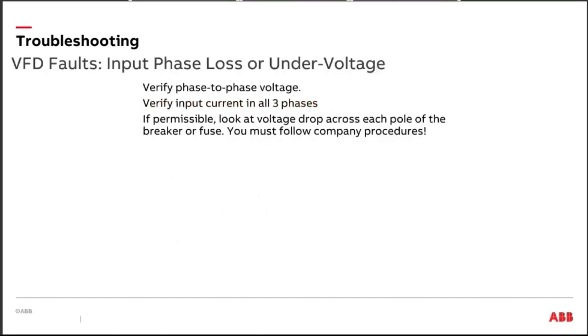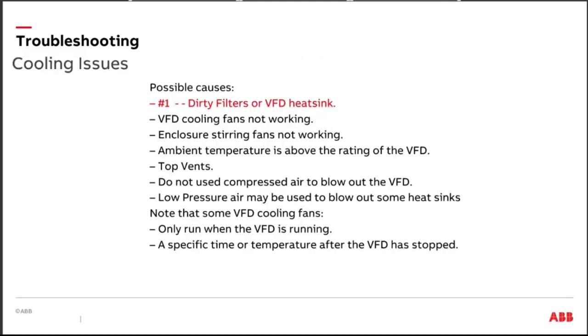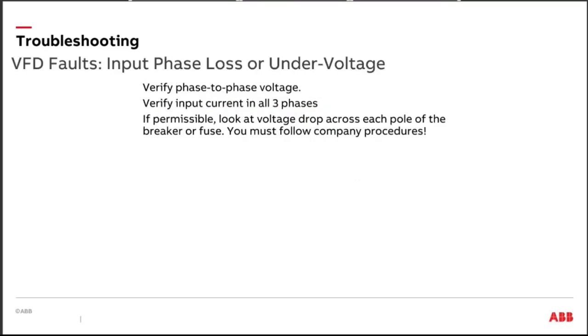Oh, another thing to remember about the fans, not just ABB, lots of people. When you shut the drive down, those cooling fans are going to continue to run. We want to bring that heat sink temperature down to a certain level, and the fans will run until we reach that level. So if that's happening, don't be alarmed about it. It's okay. That's what you should be looking for. That's something that probably should be happening.